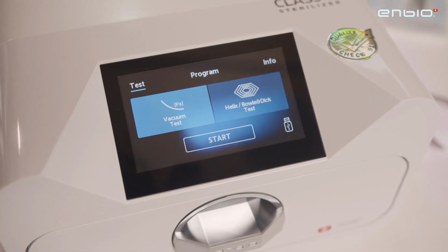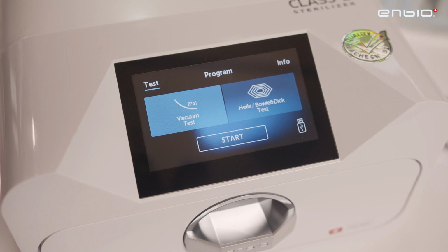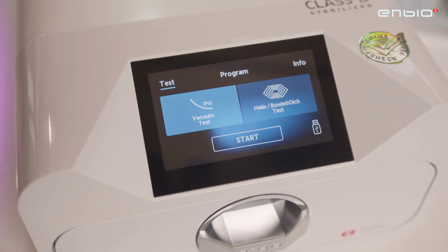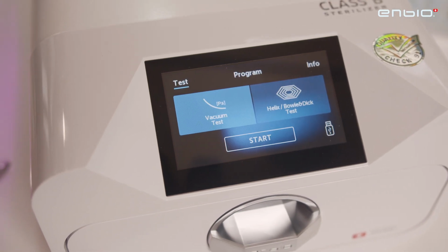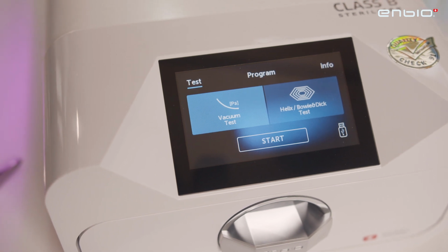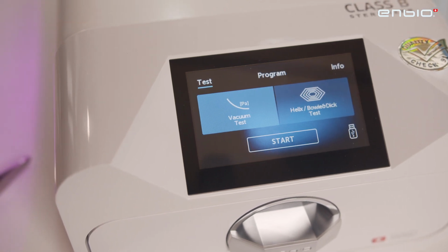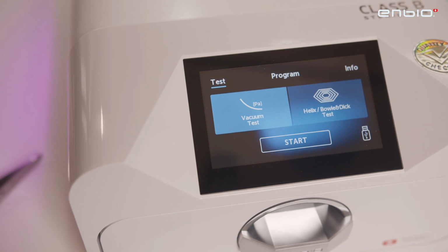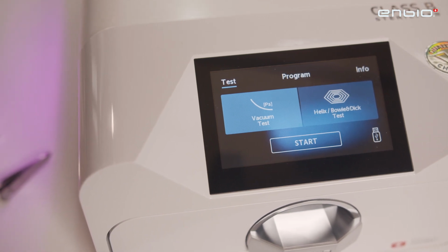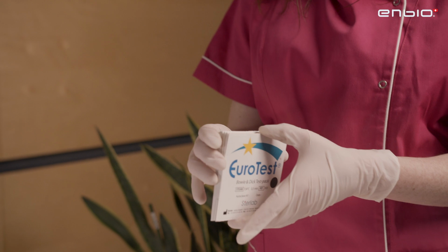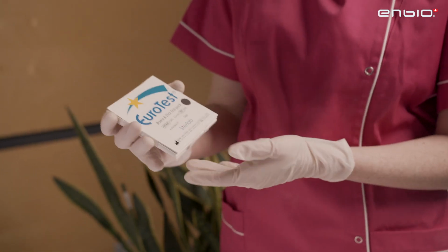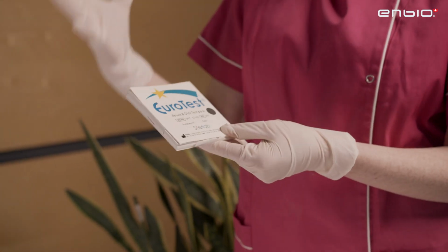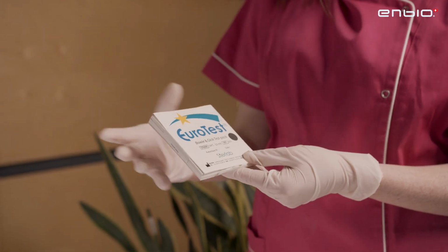And we have a special program that we have to choose in order to do this test. So in the menu of the autoclave, you have a test section where we can select the Bowie and Dick test and perform it. And now we can see if the penetration of the steam during the sterilization was correctly done.